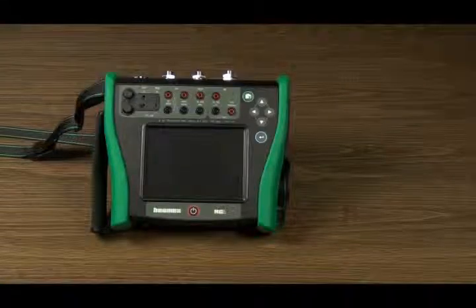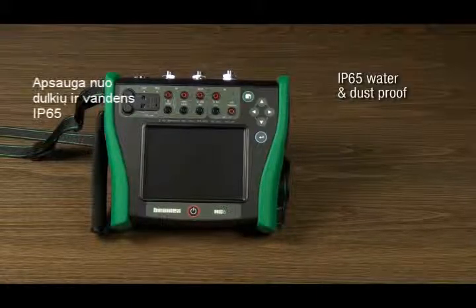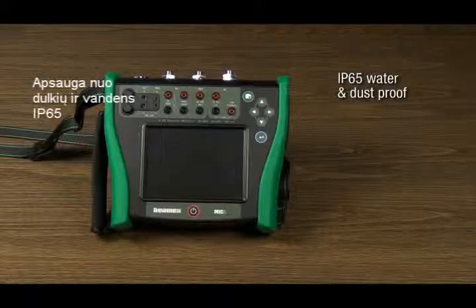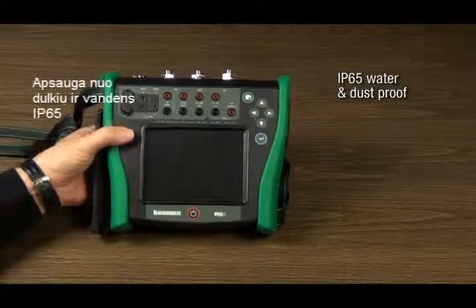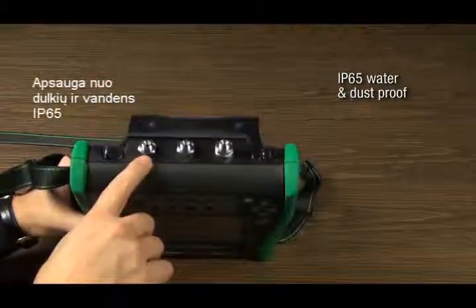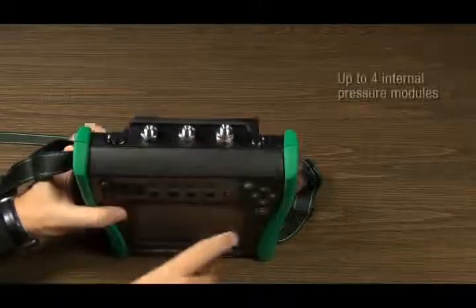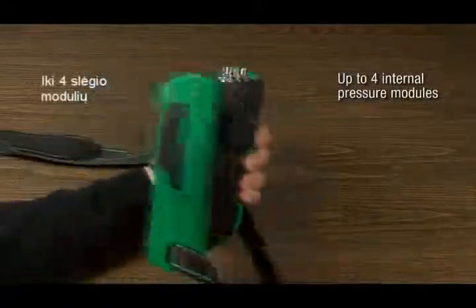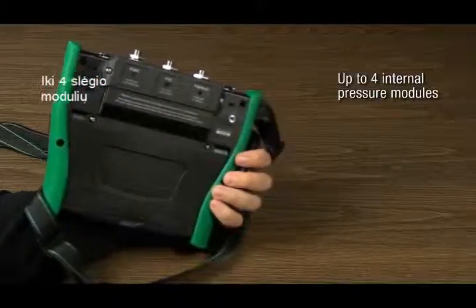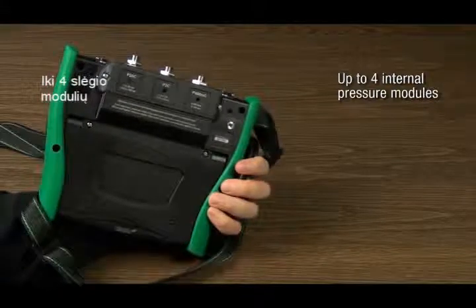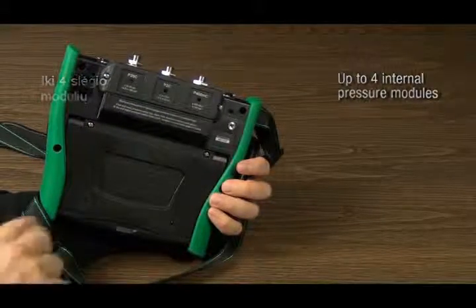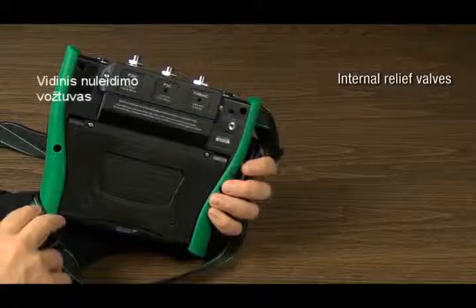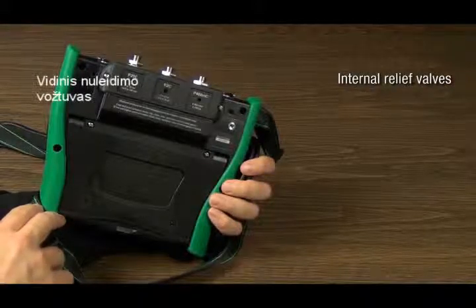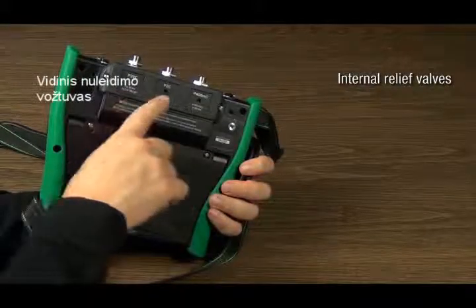The MC6 casing is IP65 water and dust proof, so it is ready for tough field environments. Internal pressure modules are located here in the upper part of the case. Up to 4 internal pressure modules can be installed simultaneously, assuming one is a barometric module. All low-pressure modules are provided with an internal relief valve for overpressure protection. Relief valves blow out from these holes in the rear panel.